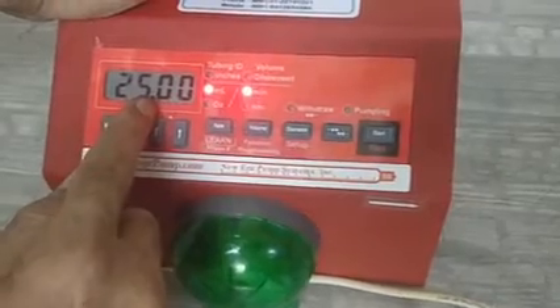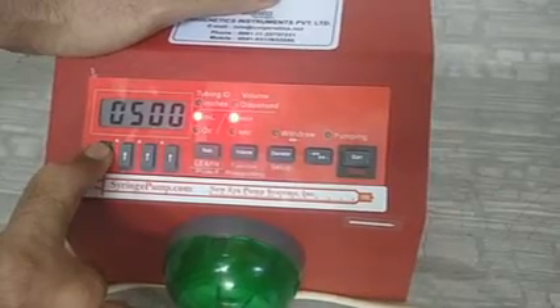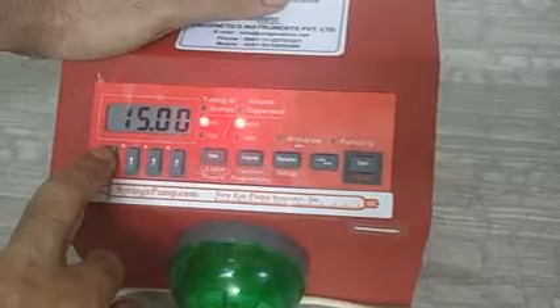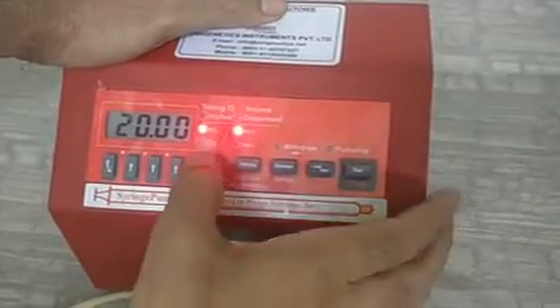Suppose I want to make a flow of 250 and I want to bring this dot to this point. What I have to do is keep it pressed, 7890, and see the arrow dot is moving. So wherever you want, you leave the dot and then set the flow. So again I am making it 20 ml per minute only. Now I have come to rate. I will select my unit first, 20 ml per minute, and my rate again I want 20 ml per minute. Again I can change it accordingly, and now I am setting my volume. Volume also I can set in the same way. At this moment I am keeping it 10 ml only.